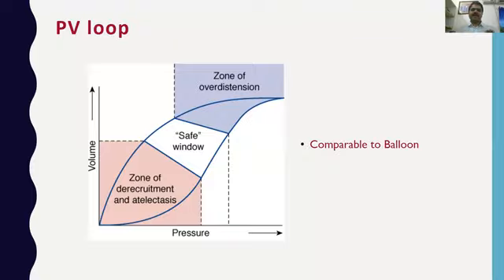But another important point, which is more clinically relevant in case of high frequency, is the expiratory limb of the PV loop. This is called hysteresis. If you gradually reduce the pressure in the lung, it won't take the same path. It won't come back like this. It will go on a different path. So initially there will be a fall in pressure, but the volume is not going to change much. And at one point, suddenly it will drop.